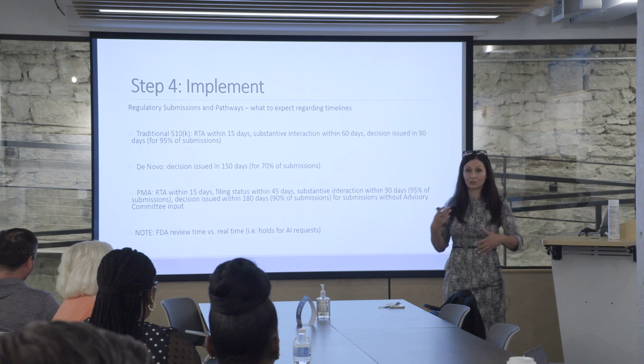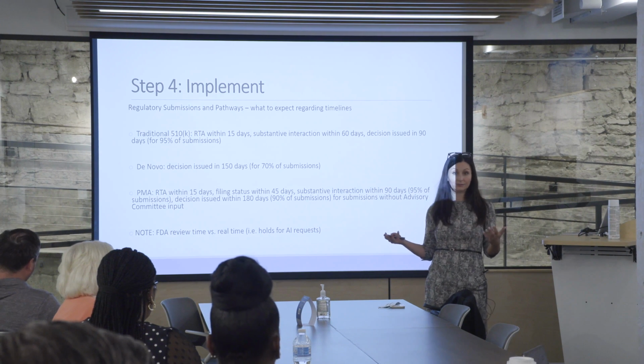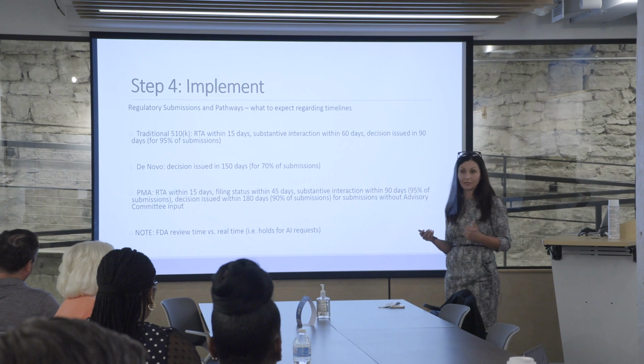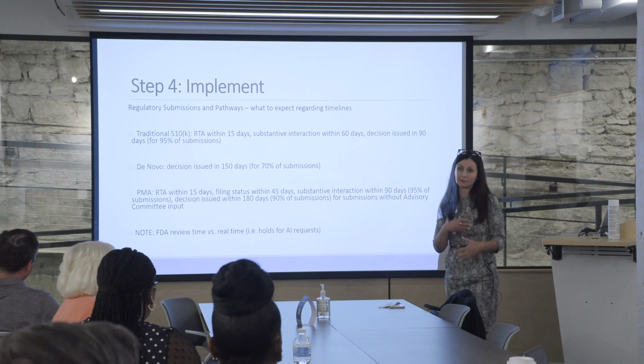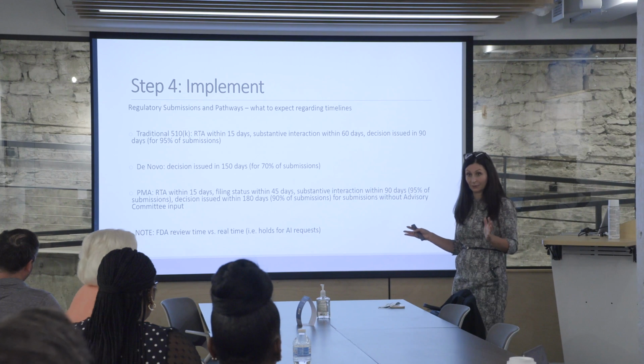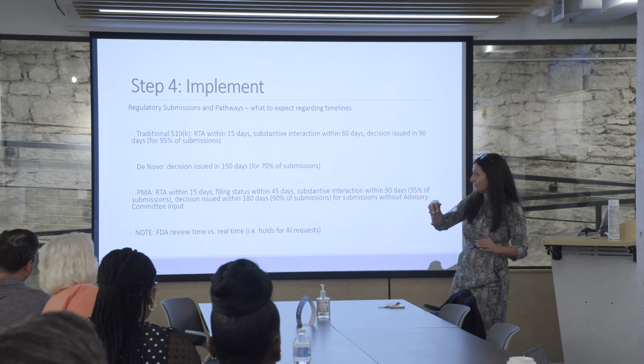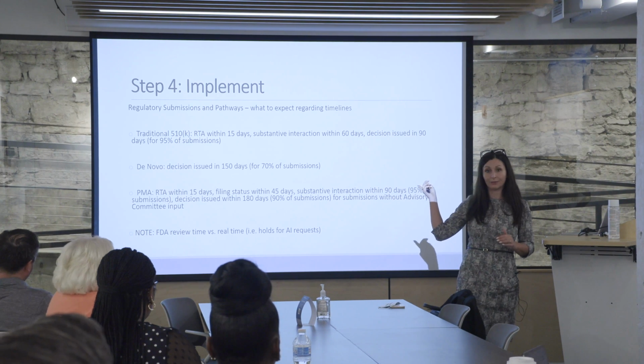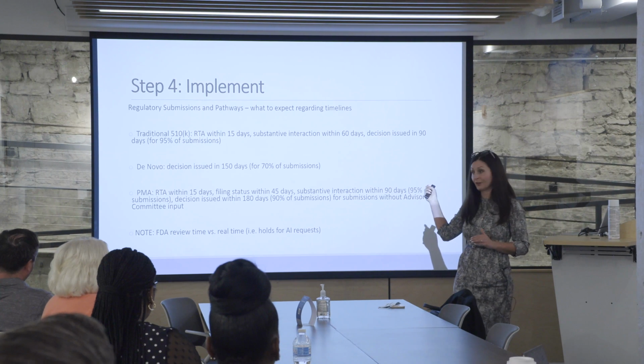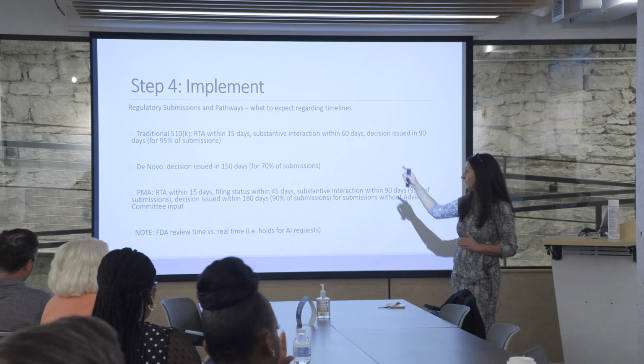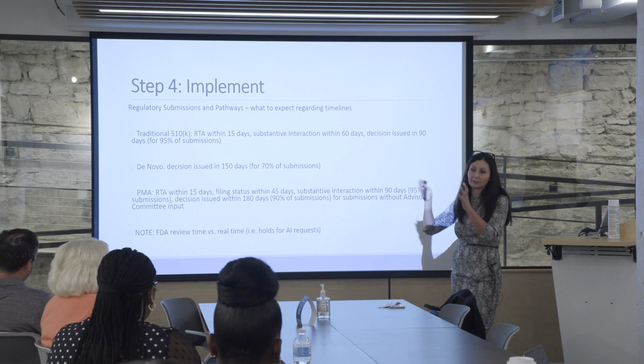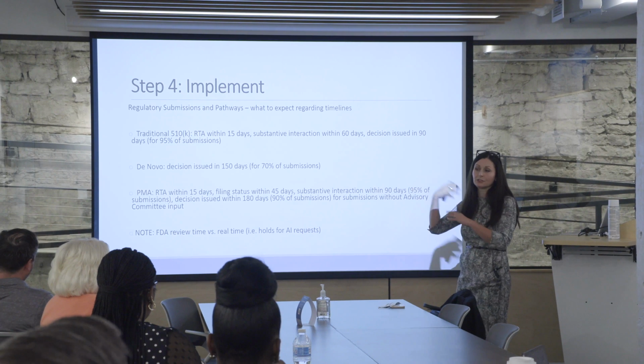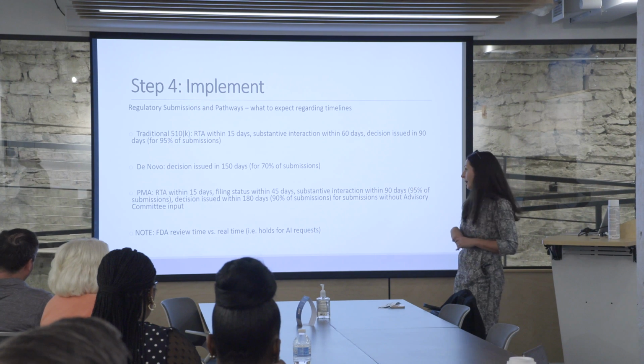So you might be able to turn that around very quickly and respond to them in a couple weeks, and that's great. Or if you need to do more testing or collect more data, it might take a little bit longer. Once you submit back to the FDA, then they have the rest of that 90-day time frame, so basically anything past 60 days, usually it's about 30 days that you have until you get your determination back from the agency.